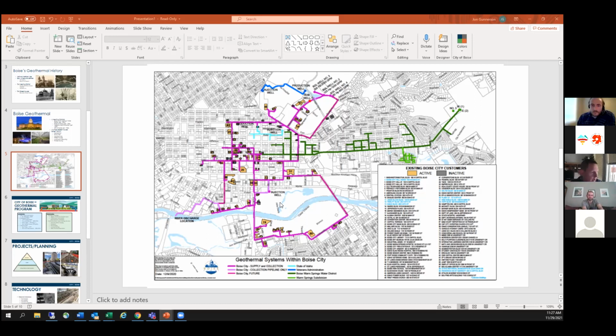The other issue we have when extending pipelines is the hydraulic aspect. Being in the business of delivering hot water, we want to get it from point A to point B as fast as we can, keeping velocities high so the water doesn't decay or cool down before reaching the end user. Going back to the example a couple blocks west of our system, ideally we want to extend large diameter pipes so we have infrastructure in place for future growth, not just the one building that requested it. Unfortunately, bigger pipes mean slower velocities, and the water has a longer residence time before reaching the end user.